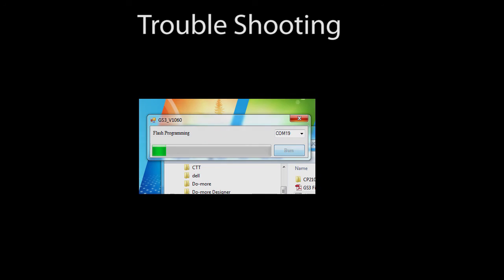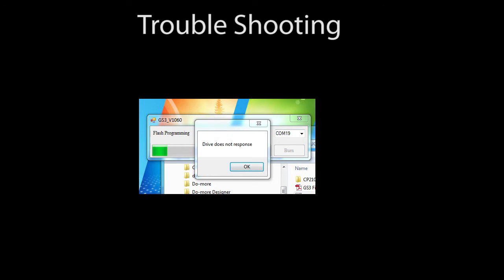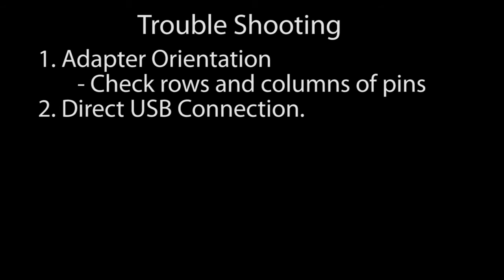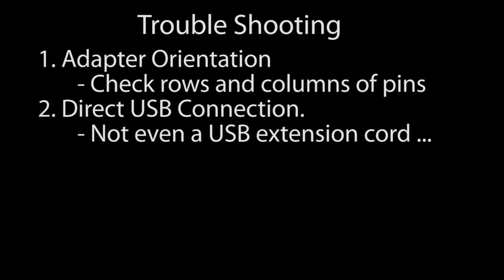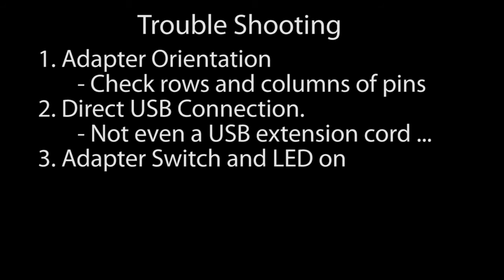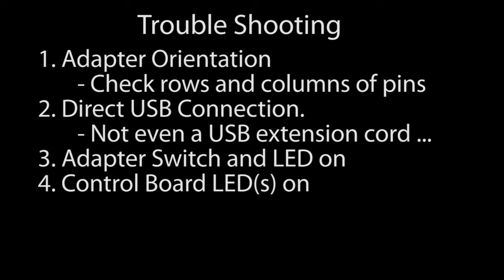If the upgrade fails for some reason or the download hangs or you see a message like this, check the following. Make sure the adapter board is oriented correctly and that the pins aren't off by a row or column. It's easy to do. If they are, don't panic, just reposition the adapter and start over. Make sure the USB connection is not going through any hubs, docking stations, port replicators, etc. We want a clean shot between the PC and the adapter. Make sure the LED on the adapter is on when the power switch is on. Make sure that one or more LEDs on the drive's control board are on when the adapter switch is on and connected to the PC via USB cable.